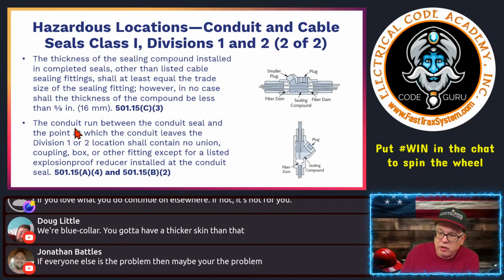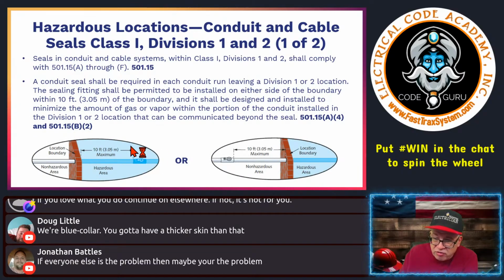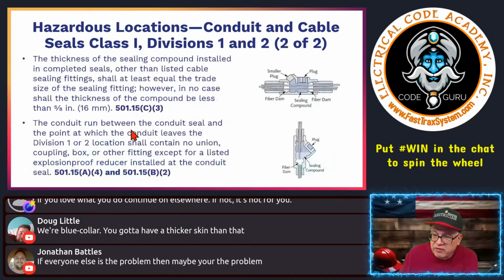It says the conduit run between a conduit seal and the point at which the conduit leaves the Division 1 or Division 2 location shall contain no unions. Remember what I said in this example right here? I like this one better because I know what the code says in this portion. And here's what it says.